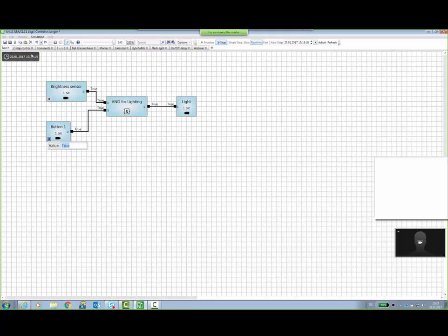You see on the upper left side, date and time. If you would like to simulate also time functions, but you don't want to wait until Christmas maybe where you have created any time functions, then you can simulate any time here. Possible with this function on the upper right side. Adjust and refresh. Adjust means I can change here the time. I say, come on, I would like to simulate the 28th of January at any time. And then I can adjust, and you see here on the left side in my worksheet, the new time will be adjusted. Now maybe your time function will run because it's related to this time I have adjusted here. If I say refresh, then it goes back to the real time. So also time functions you can in principle simulate here.